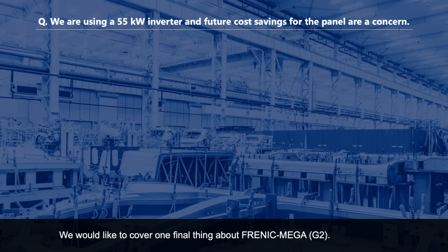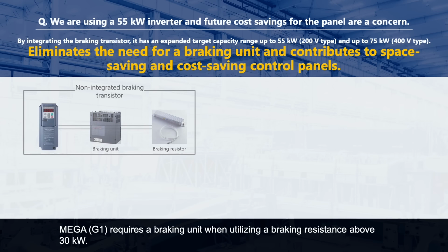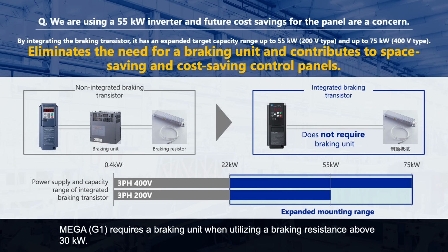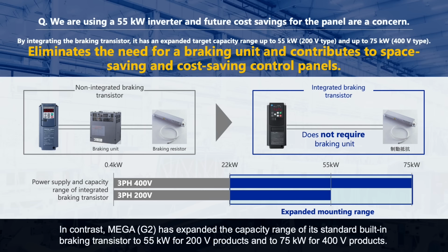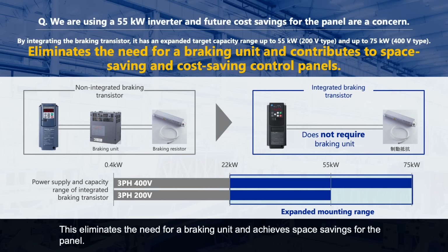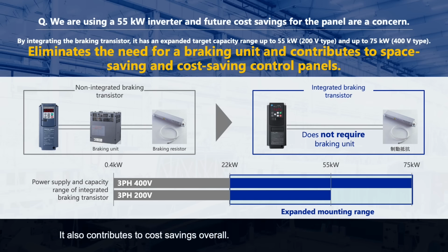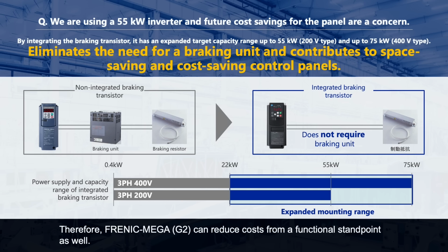We would like to cover one final thing about FRENIC-MEGA G2. If you currently use a 55 kilowatt inverter, you can reduce the panel cost. MEGA G1 requires a braking unit when utilizing a braking resistance above 30 kilowatts. In contrast, MEGA G2 has expanded the capacity range of its standard built-in braking transistor to 55 kilowatts for 200 volt products and to 75 kilowatts for 400 volt products. This eliminates the need for a braking unit and achieves space savings for the panel. It also contributes to cost savings overall. Therefore, FRENIC-MEGA G2 can reduce costs from a functional standpoint as well.